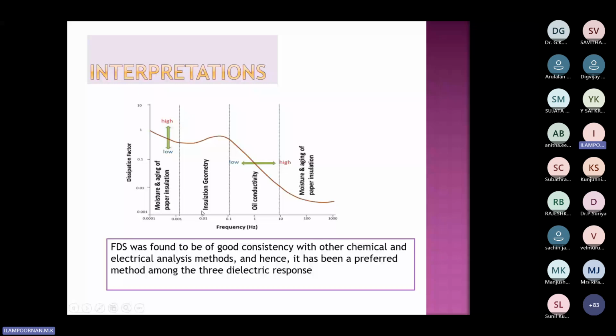What are the actual design parameters in the transformer? If I move higher in frequency, from 0.1 hertz to 10 hertz, I can understand what is there in the oil. It's like scanning a particular person - my beautiful transformer is getting scanned. If I apply a very low frequency signal, I'll get what is happening in the insulation. If I apply a medium frequency, I'll understand how the inside structure is. And if I apply very high frequency, I will understand what is actually happening.